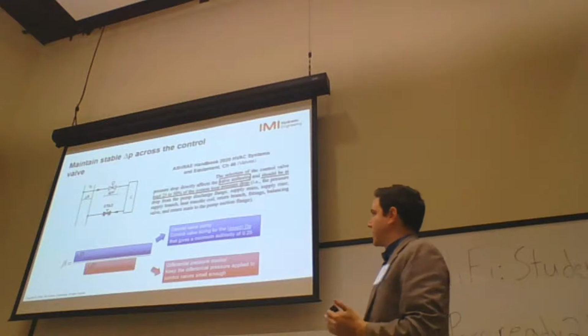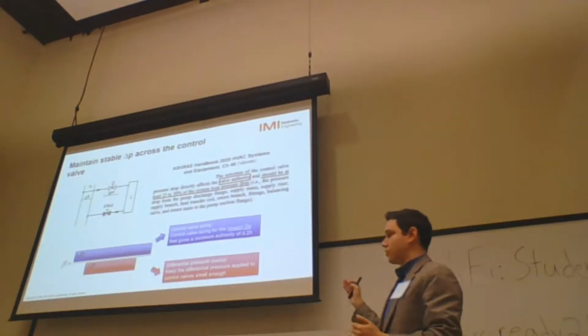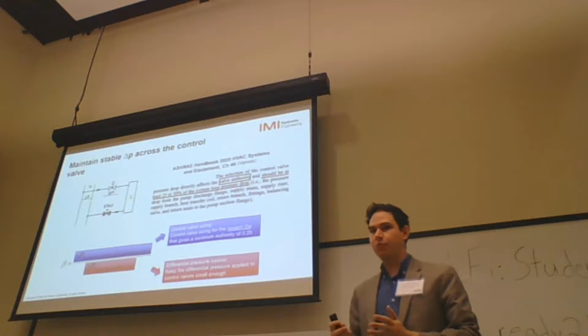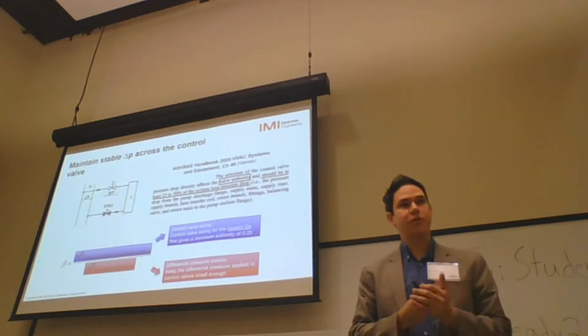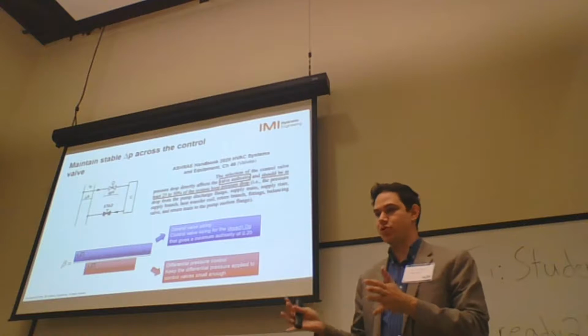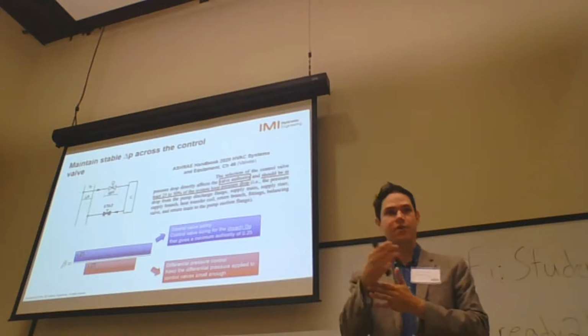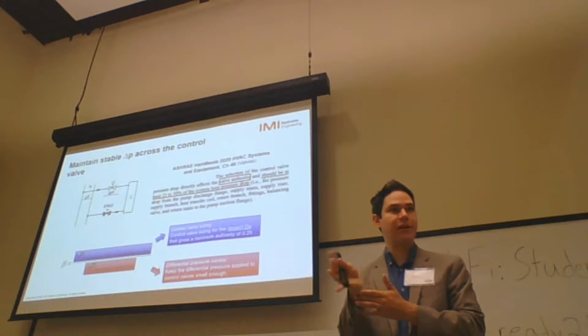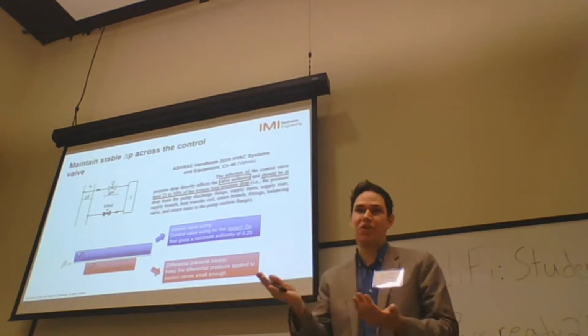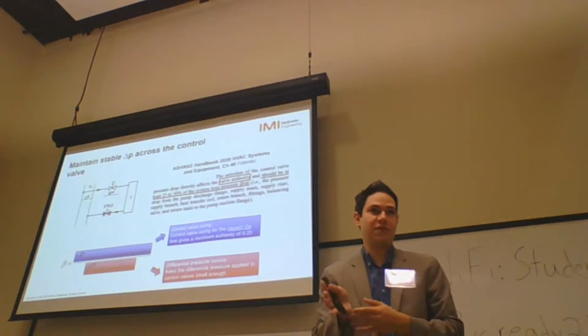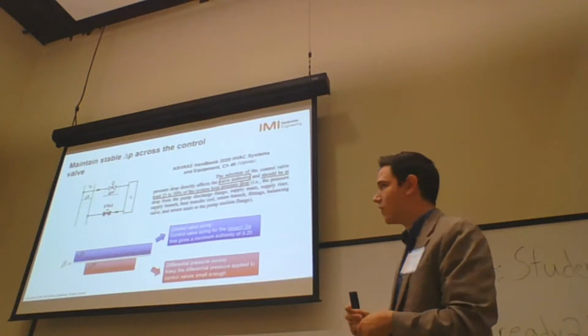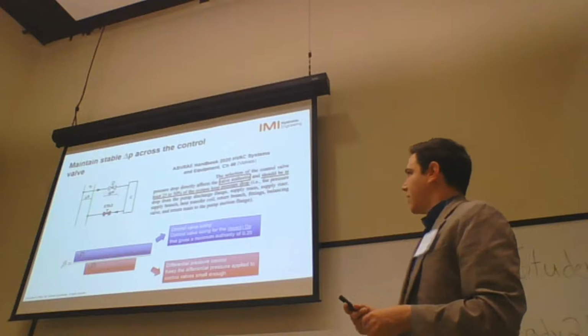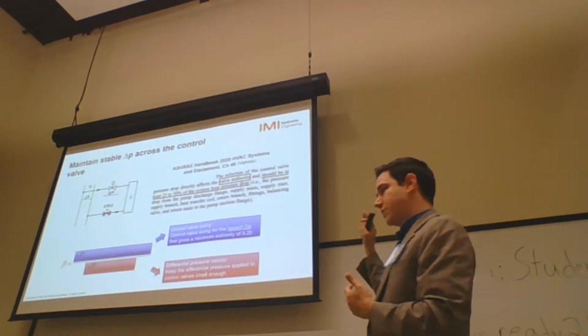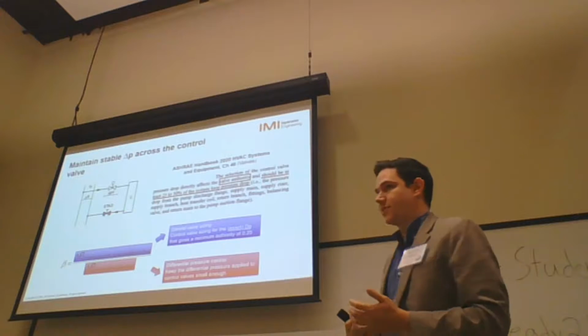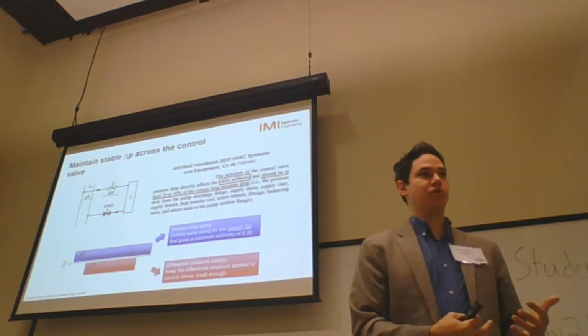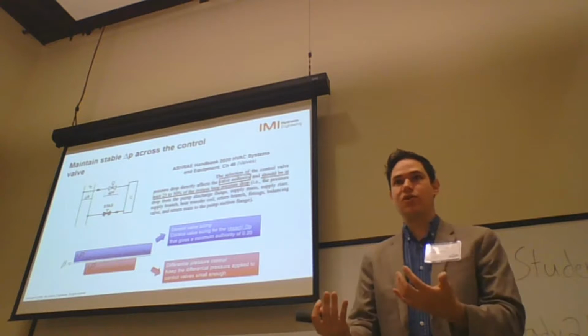The next part is to maintain a stable differential pressure across the control valve. For us, the extremely important part is that many times we go to a job site and see a control valve always hunting, always moving up and down if it's a globe style, or if it's a ball valve, always rotating, closing and opening. What is important to discuss is that this is mainly a problem of the selection of the control valve. There's not much we can do on the job site.